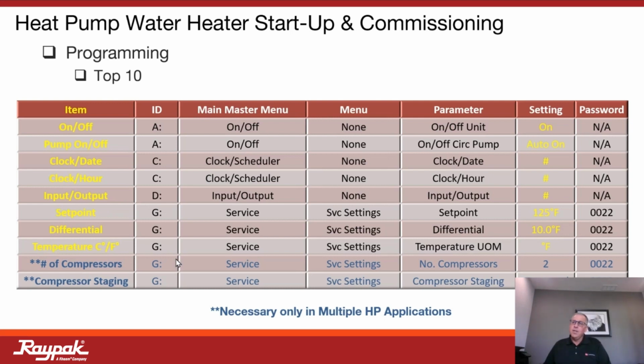This one is important: unit of temperature, unit of measure. The default is Celsius. Sometimes we get them into our factory that it's already been programmed to Fahrenheit. But again, very easy to navigate to this menu, the G menu, toggle over to service. The up and down arrows will navigate you to that individual parameter of temperature unit of measure. You hit enter. We can select the up and down arrow to select Fahrenheit, hit enter, and it'll again ask us for this password, and off we go.